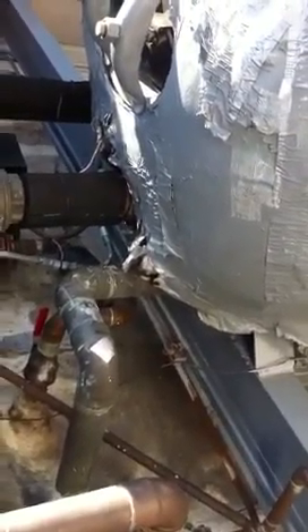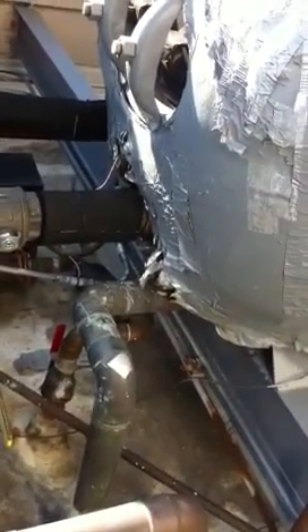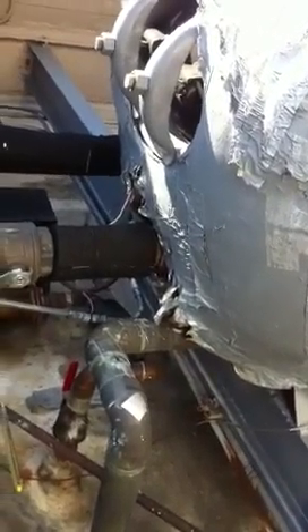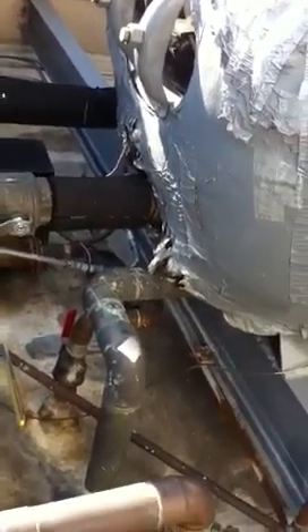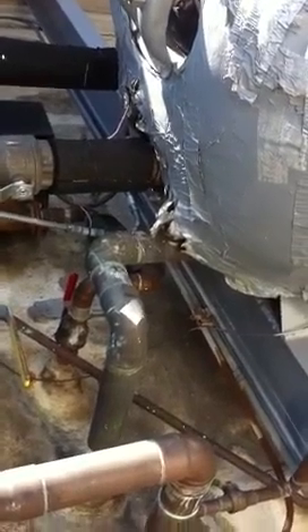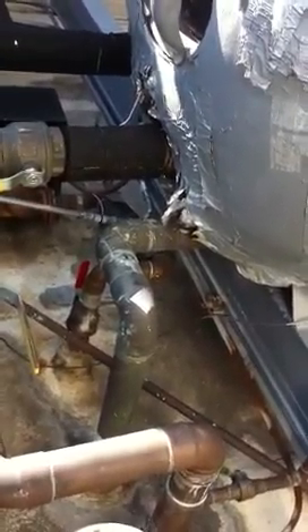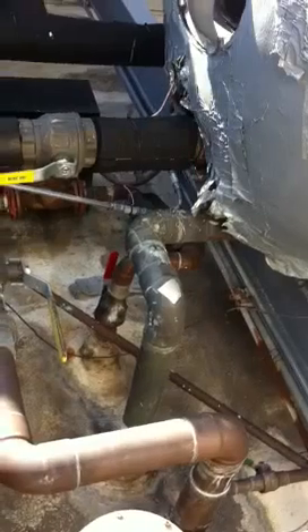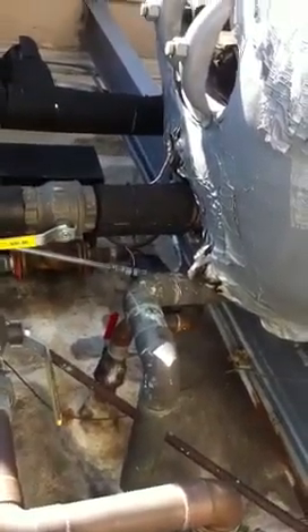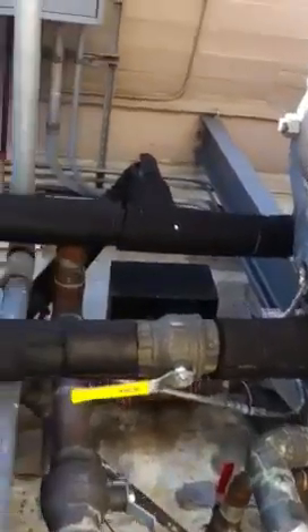And the manifold piping on the boiler, which is all the boiler piping that connects to the tank manifold piping, is going to be repiped just because it's worn out and thin on the inside. So you have the boiler piping and you have the manifold piping. Manifold piping is the boiler piping. Okay. Yeah. And then your tank piping. And then you're going to put everything back on the existing manifold, correct? That's right. Yeah. The new tank is going to be custom built.